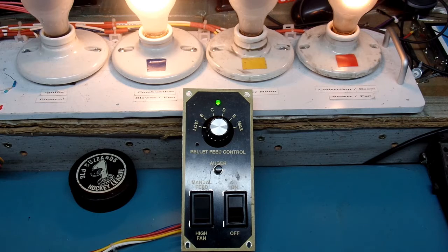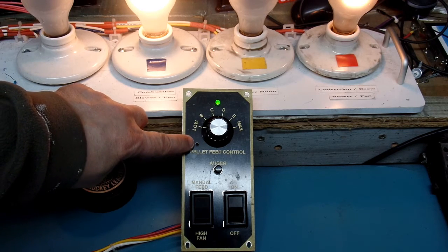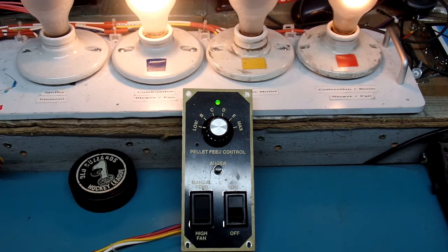So let's just let it time through here, and we'll see the auger drive come on and then off. It'll be on for a short period of time and off for a longer period of time, approximately 20 seconds off and 2 to 4 seconds on, really quick. So you saw that it worked. We have a little light just above the word pellet. There's a through hole on the faceplate. There's an LED on the back that you can see when the controller is trying to drive the auger motor. There it goes again. So that's functioning in low.